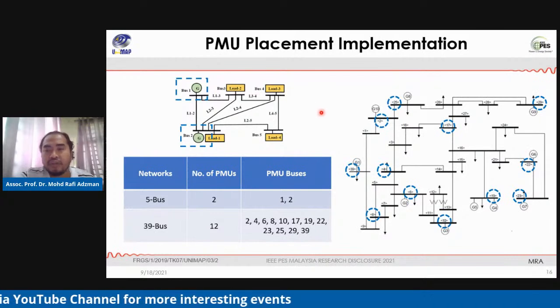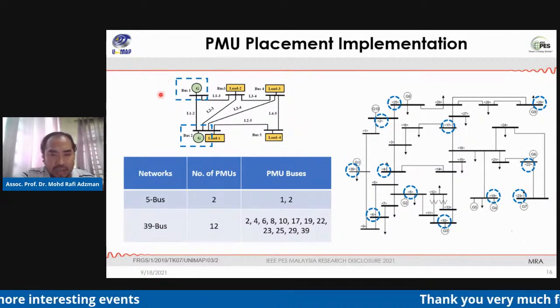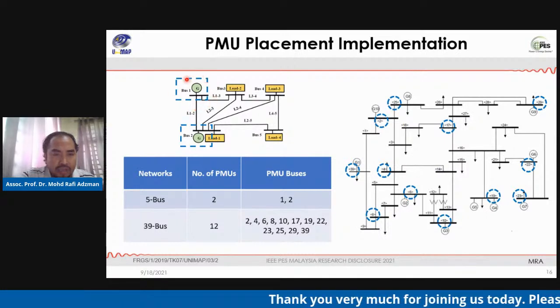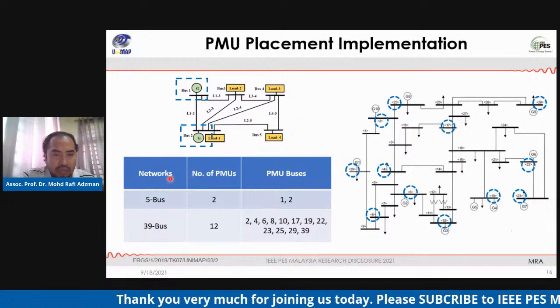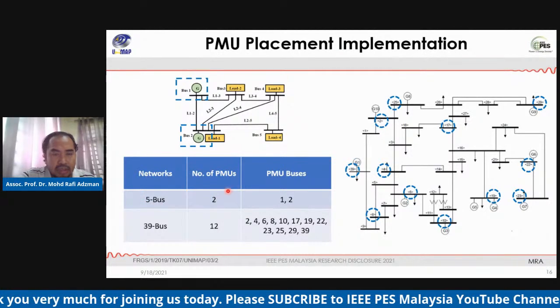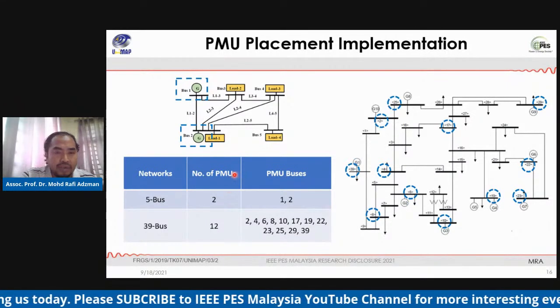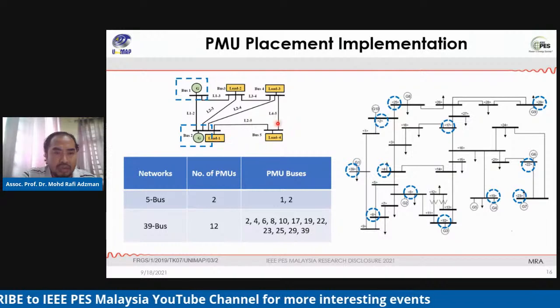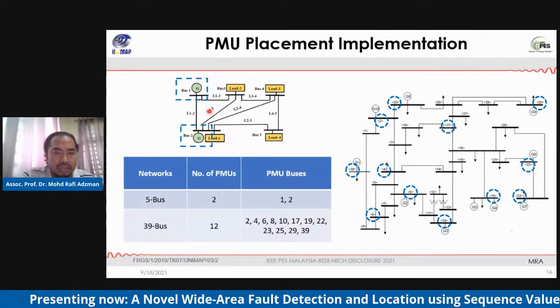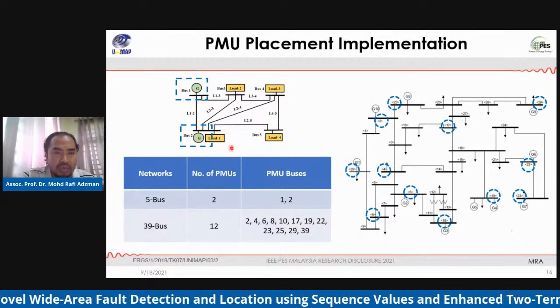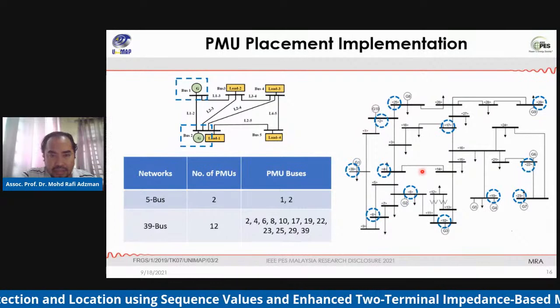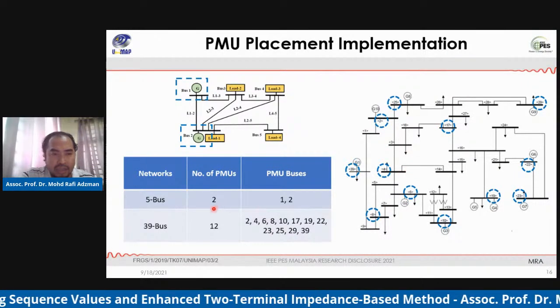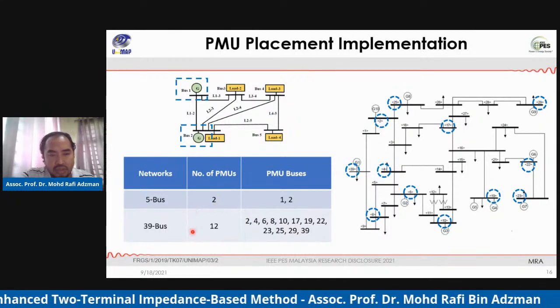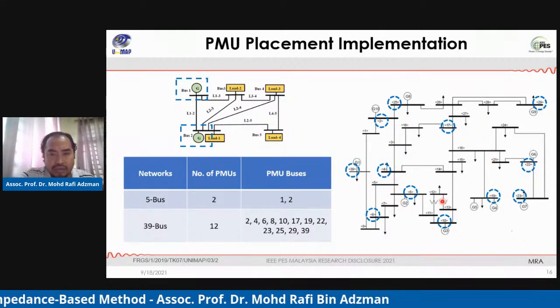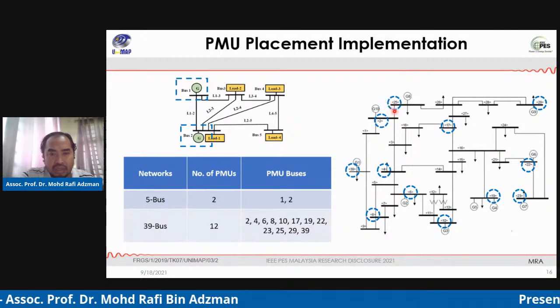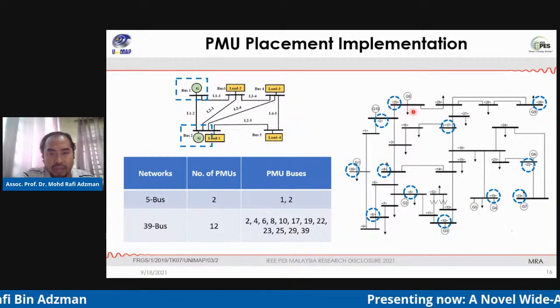Okay, here is the result for the 5 bus and 39 bus networks. The dotted blue circle is the location of the PMU. For example, for the 5 bus network, based on the PMU placement strategy, we found that we need 2 PMUs for all these buses, located at bus number 1 and bus number 2. While for the 39 buses, based on the PMU placement strategy, we found that we need 12 PMUs. So these are the PMUs located at the buses.